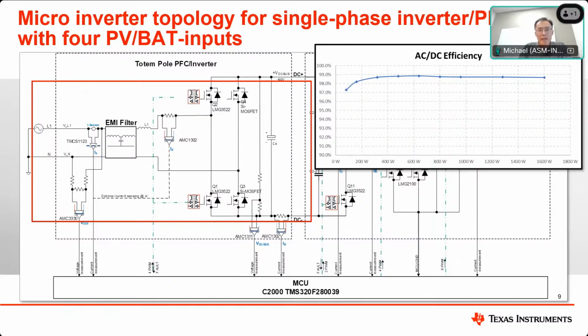If we combine all together, the complete converter shows from DC input all the way to AC output a weighted efficiency of over 95%, which is remarkable for a fully bidirectional converter compared to the low-cost unidirectional current source inverters that often achieve only in the lower 90% range.